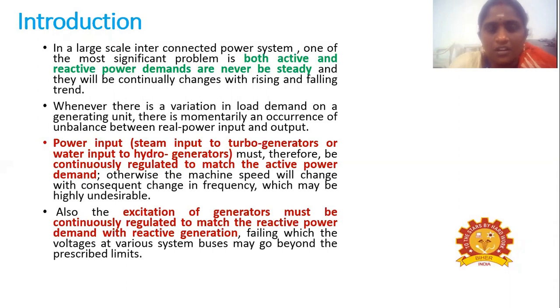We have to rectify this problem by regulating the power input to the generators and by regulating the excitation of the generators. If we regulate the power input to the generators to match the active power demand, then we can maintain a constant frequency. If we regulate the excitation of the generators to match the reactive power demand, then we can maintain a constant voltage.